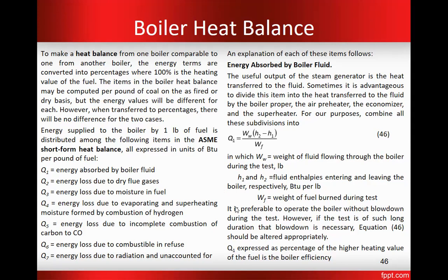It is preferable to operate the boiler without blowdown during the test. However, if the test is of such long duration that blowdown is necessary, equation 46 should be altered appropriately. By heat balance, Q1 expressed as a percentage of the higher heating value of the fuel is the boiler efficiency.